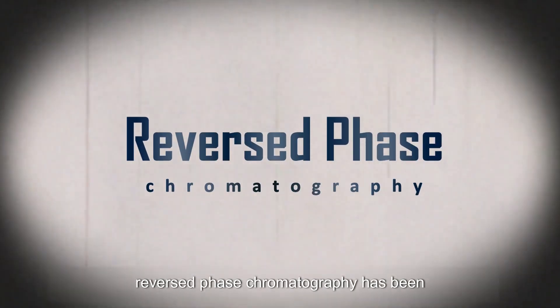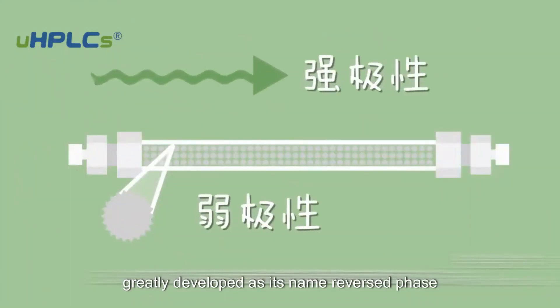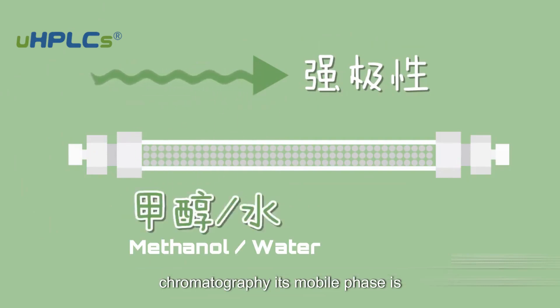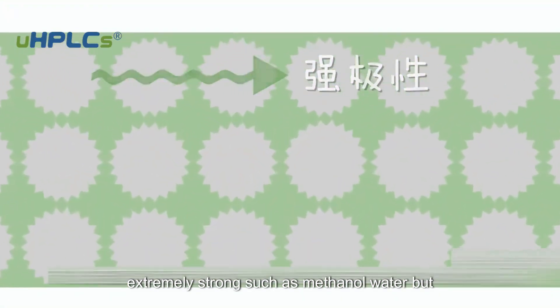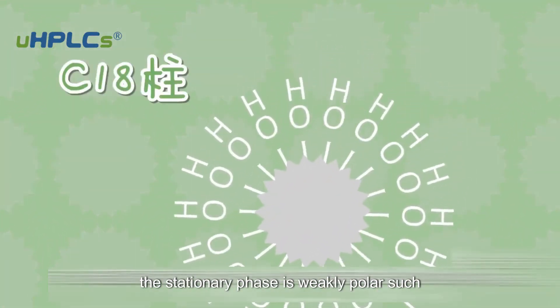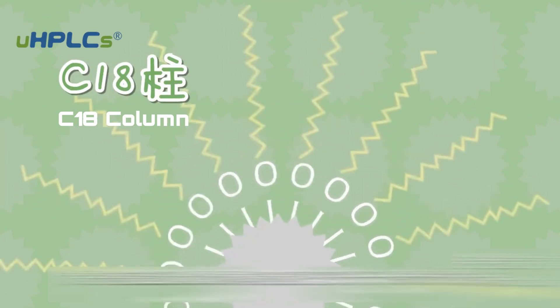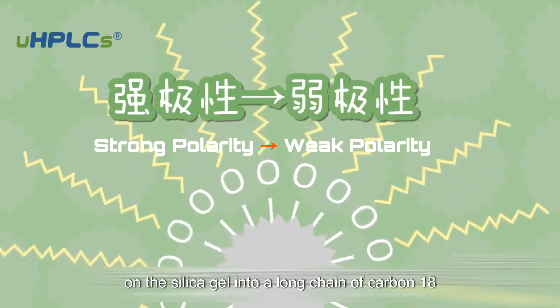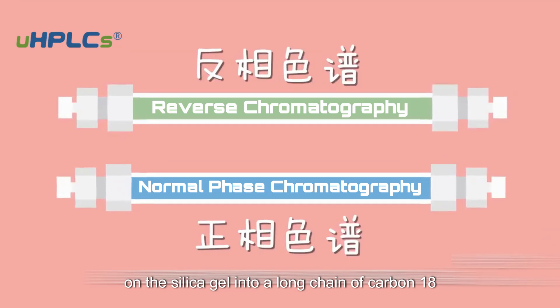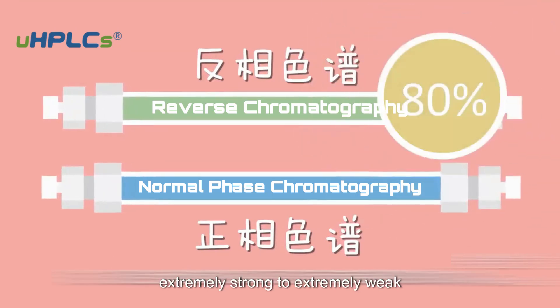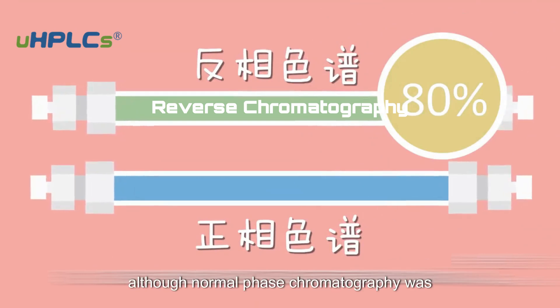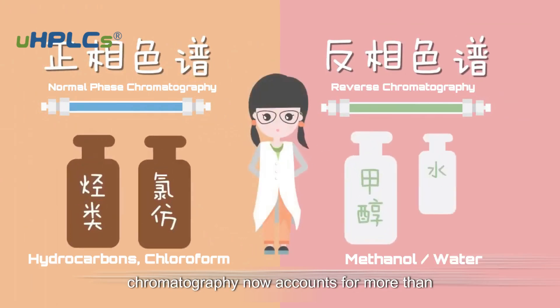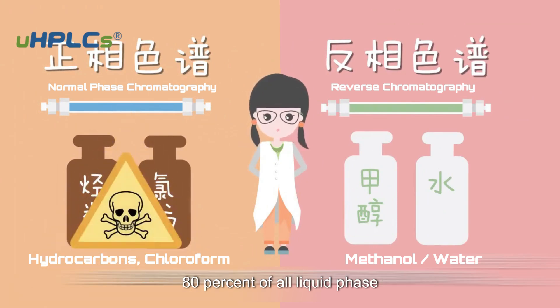After chemists became accustomed to the chemical bonding technology of silica gel, reversed phase chromatography has been greatly developed. As its name implies, reversed phase chromatography is the reverse of normal phase chromatography. Its mobile phase is strongly polar, such as methanol-water, but the stationary phase is weakly polar, such as an octadecyl silica gel column, also called a C18 column. It converts the original silanol groups on the silica gel into long C18 carbon chains, changing the silica surface from strongly polar to weakly polar. Although normal phase chromatography was invented first, it is not widely used. The application of reversed phase chromatography now accounts for more than 80% of all liquid chromatography applications.